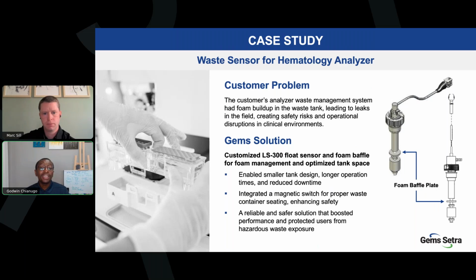We also incorporated a magnetic interlock switch as part of the solution. This safety feature prevents waste from being pumped into the tank unless the container is properly sealed in its receptacle, meaning operators are better protected from accidental exposure to hazardous biological waste, a top priority in hematology labs.